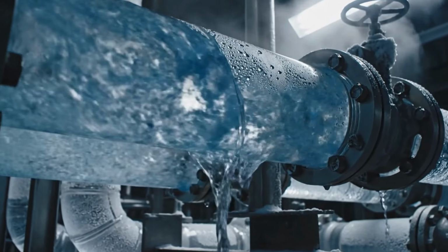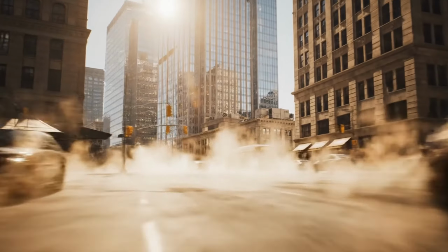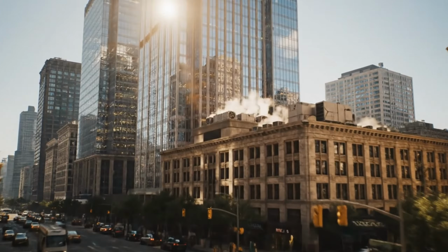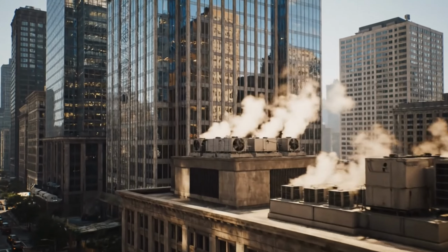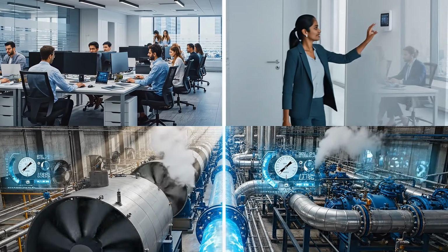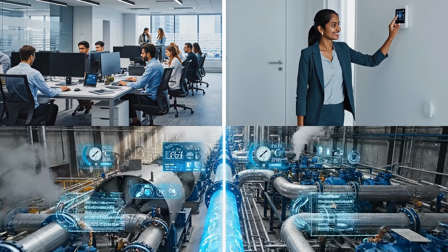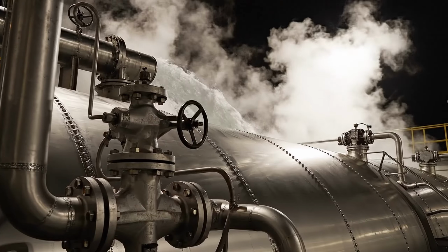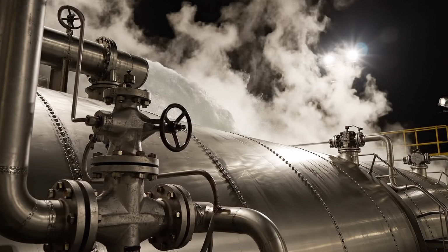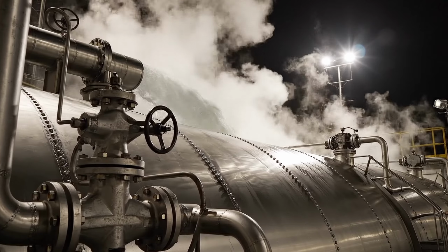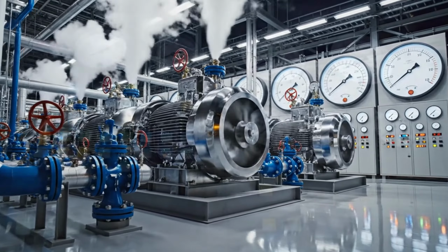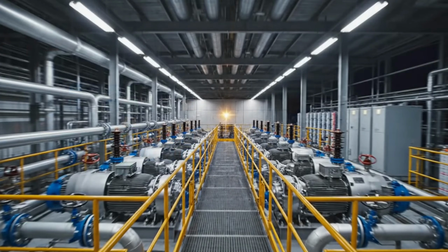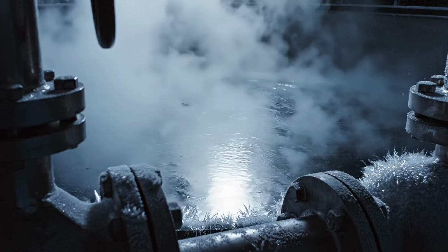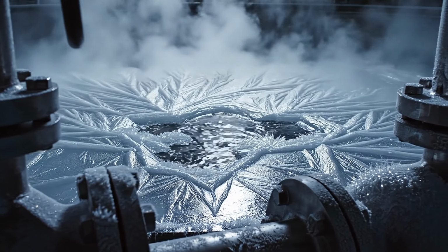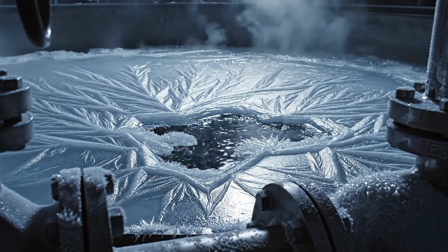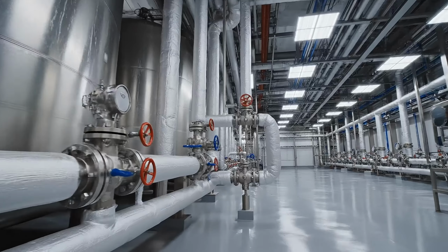The core issue was what engineers call plug load diversity. Essentially, the building's mechanical systems had been designed around a worst-case scenario. Every tenant running maximum equipment on the hottest day of the year simultaneously. In reality, that scenario almost never happens. But the equipment was permanently sized and permanently running as though it would. The engineering solution was a complete chilled water plant overhaul. The original system was replaced with a centralized plant using variable speed chillers, machines that can dial their output up or down in real time based on actual demand rather than theoretical maximums. This alone was a radical shift in how the building consumed energy.